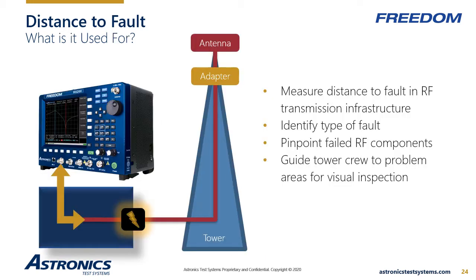The FREEDOM R8200 VNA's distance to fault tool measures reflected signal level over distance. This type of measurement is the key to sweeping cable runs to identify the location of suspected faults. Using the system settings, potential faults can be evaluated by magnitude and failure mode. Locate opens, shorts, kinks, corrosion, water ingress, loose connectors, human or animal-caused damage.